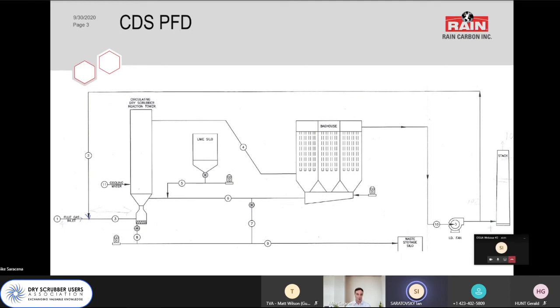Over the last year, we've really got these things lined out. We don't really have corrosion issues anymore. The stack, as I mentioned, at Lake Charles had the highest corrosion. It was so bad we had to replace it after just a few years of operation. So the stack was the worst part we saw from corrosion.